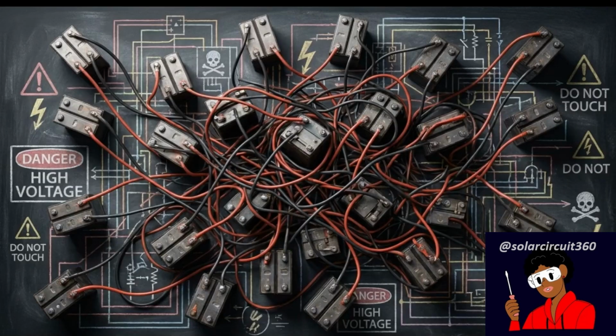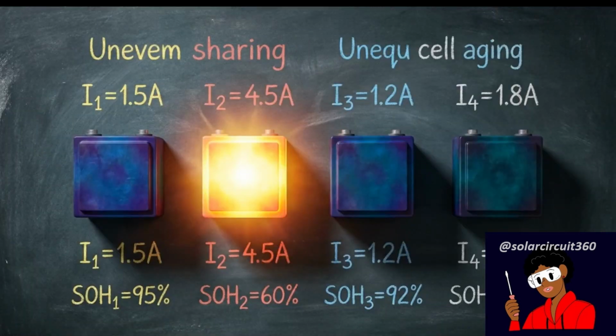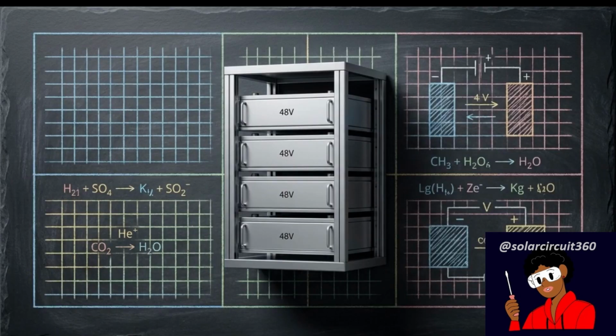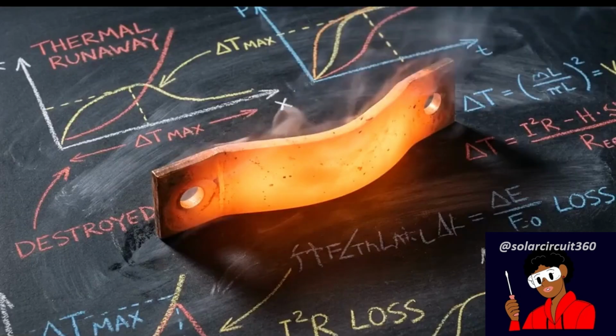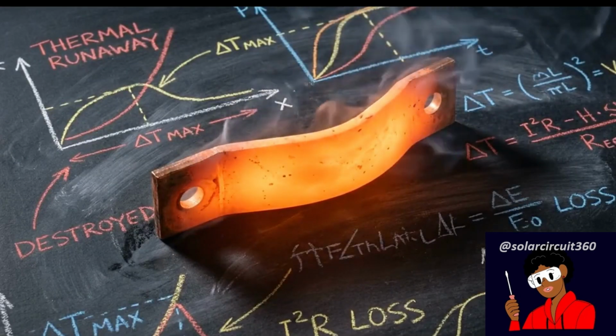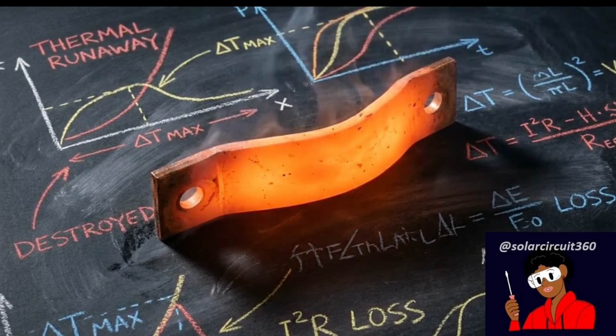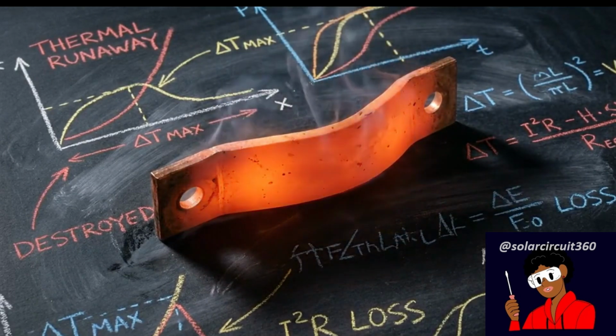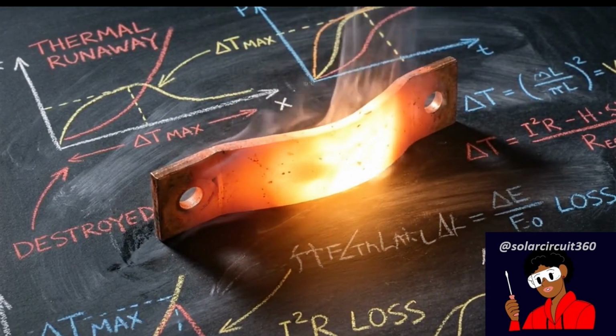To compensate for the enormous amperage of low-voltage setups, builders often wire massive strings of batteries in parallel, which inevitably leads to uneven current sharing and unequal cell aging. Stepping up to 48 volts preserves your hardware simply by shifting the internal chemistry into a far less aggressive operational state. Unmanaged electrical energy never disappears. It simply converts directly into destructive, highly localized heat that attacks the surrounding physical structure.